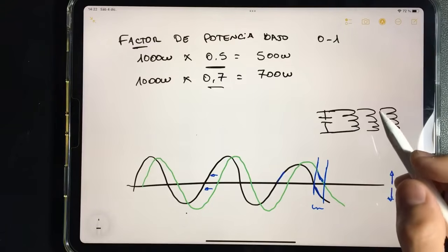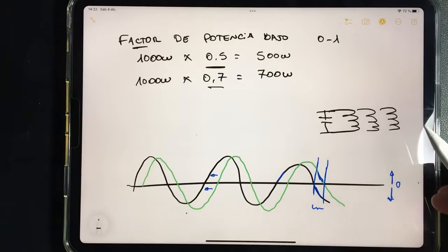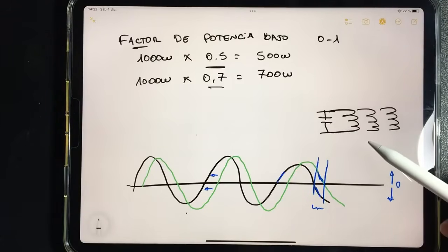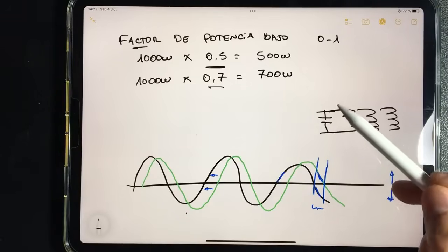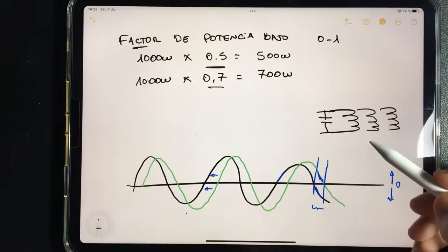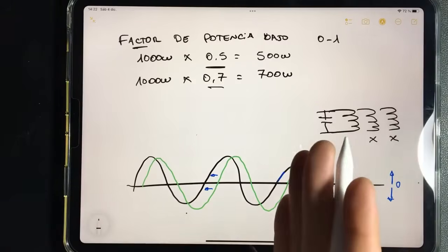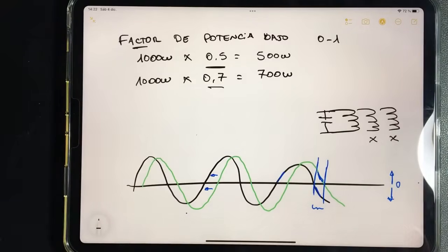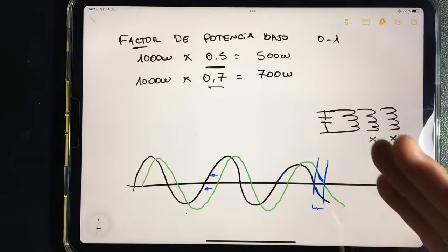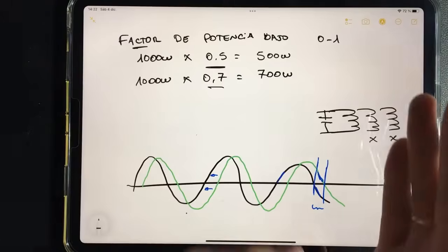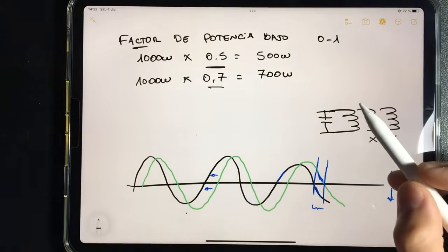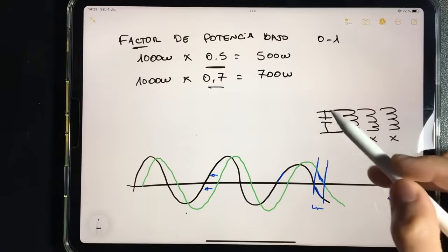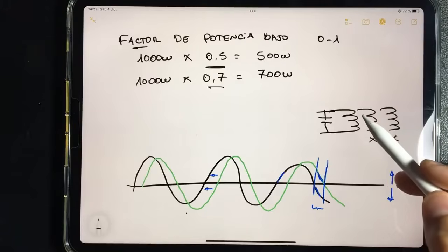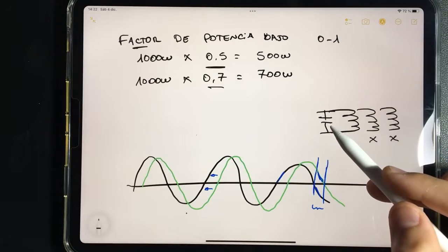But placing capacitors, unless it's a computerized capacitor bank, isn't safe, because it really depends a lot on how many machines are turned on at that moment. If I place capacitors taking into account all motors turned on, but some motors aren't on, I'll push the line to the other side, and in the end alter the power factor again. So placing capacitors isn't the safest option, but it always helps. If I have too many capacitors in one place, my power factor is also altered, and what I have to do to compensate is place coils.